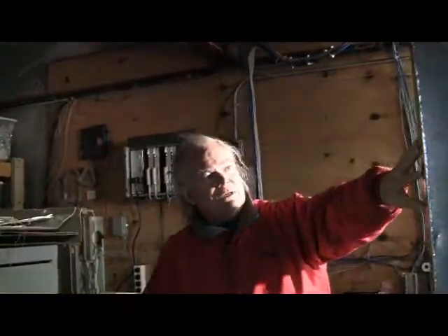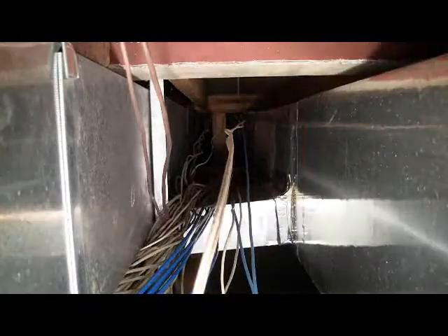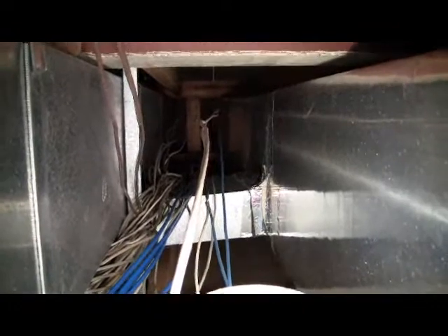I was up in the attic earlier and found this combustion air duct that is designed to bring air from the attic down to the combustion appliance zone here in the basement. This duct exists inside of an open building cavity that goes all the way up to the attic, as you can see. So we've essentially got what amounts to a straw inside of a straw.